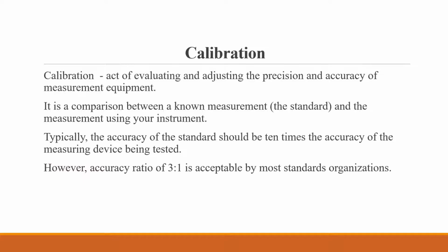Calibration. Many times we may be confused between calibration, quality control, and validation. I want to be very technical about this. What is calibration? It's an act of evaluating and adjusting the precision and accuracy of the equipment measurement. It is a comparison between a known measurement, which is the standard, and the measurement using your instrument. What you do is compare it with that standard. That standard should be 10 times the accuracy of the device being tested, but that is a very strict qualification.